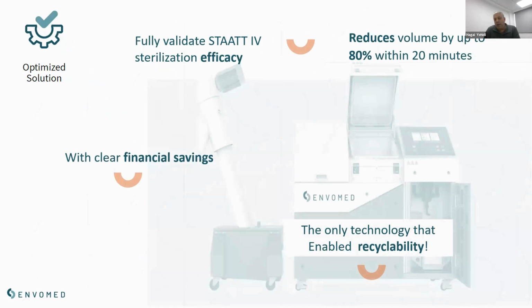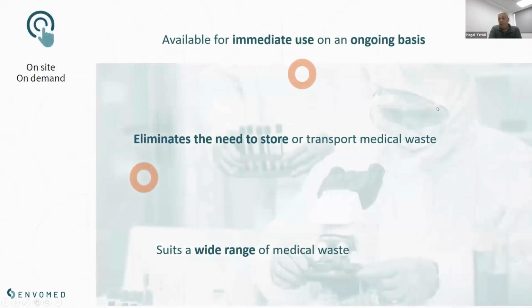It's fully validated. We did around 1 year of validations before we went to the market, before we started to market our machine. And the validation shows and proves that the waste is totally clean and without any microbes after the treatment. And what is very relevant to our webinar, and it's very, very important, is that this is the only technology that enables recycling of the plastics or of the waste after the treatment, which you cannot find when you do the heat process, because after the heat process the plastic is melted and it's very difficult to recycle it.